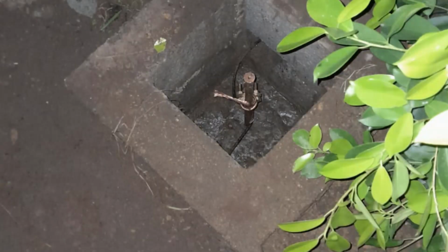Okay, so if you are at a stage of doing your earthing, or even if you're not, please bear this video in mind. Save this video. Make sure your electrician does the correct job in electrical installation. Does the correct job in electrical testing. Don't forget, after electrical systems have been installed, there are tests that are carried out. Earth resistance test, insulation resistance test, and so on, so forth. I've covered this in a previous video. Okay, that test must be done. If you can get somebody from ECG to do it, then that's fine. That's even better. But if not, anybody else who has the tester and is experienced can do the test for you. Contact us if you need to get it done. We have people who do it as well.